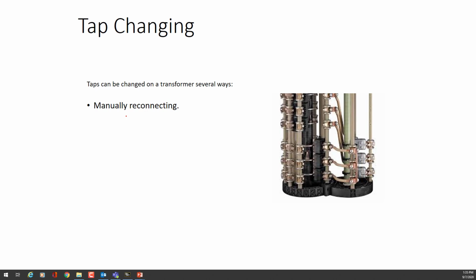Are these transformers in parallel? What's the situation? If they are in parallel, I have to disconnect all of them to avoid any backfeeding before I go and lift that wire off. So very important, make sure you are completely de-energized in any way, shape, or form before you attempt to do this. Most of the time, like if you're doing a commercial, usually it's 600 volts coming in, then you'll feed 600 volt feeders out, and it'll drop down to 120/208. You can usually isolate that pretty well. They don't usually put transformers in parallel, but when you get into any larger distribution, you might see transformers in parallel. So moving connecting bars, that's another way to do it.